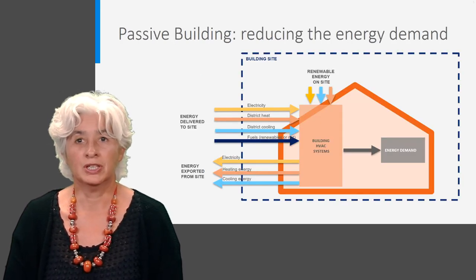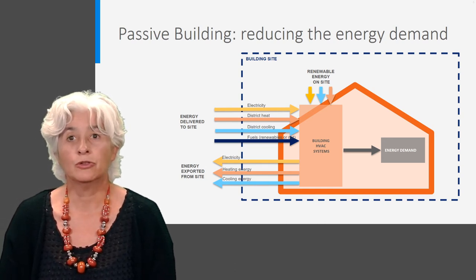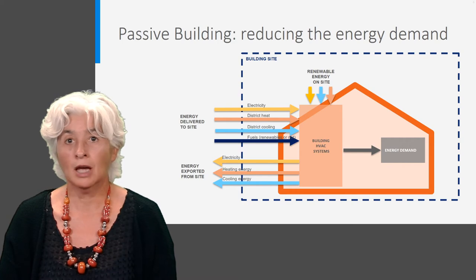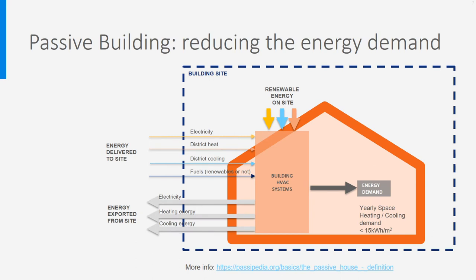Let's start with passive buildings. The main idea is to reduce energy demand as much as possible, thereby strongly reducing the energy delivered to the site. We speak of a passive building if the yearly energy demand for space heating is below 15 kWh per square meter, and the total energy demand — for space heating, appliances, hot tap water, etc. — should be below 60 kWh per square meter.